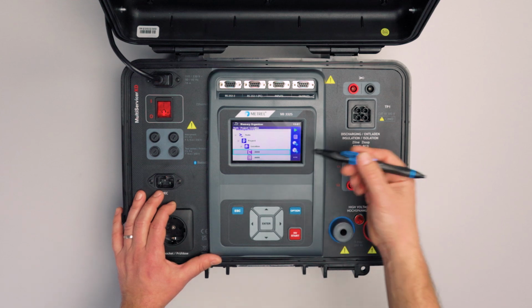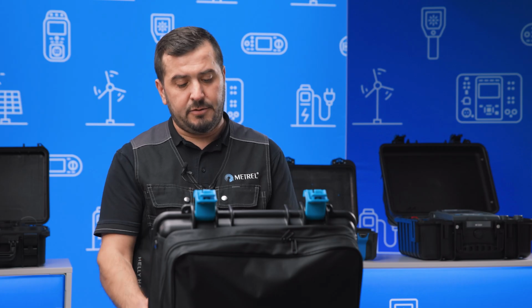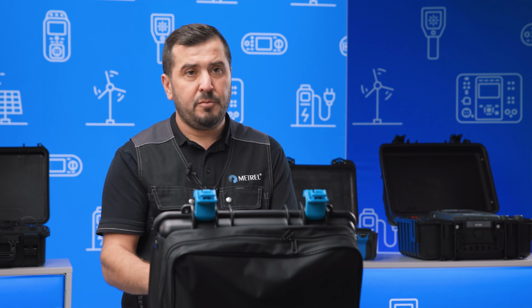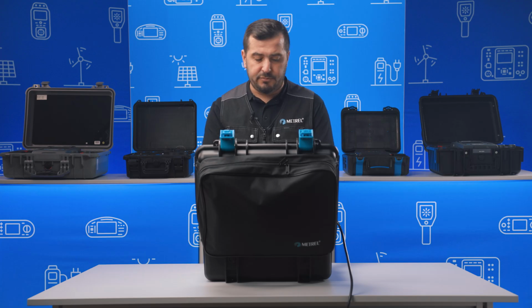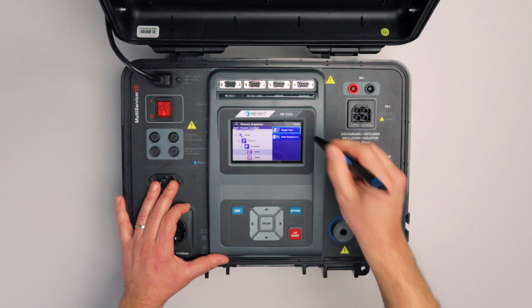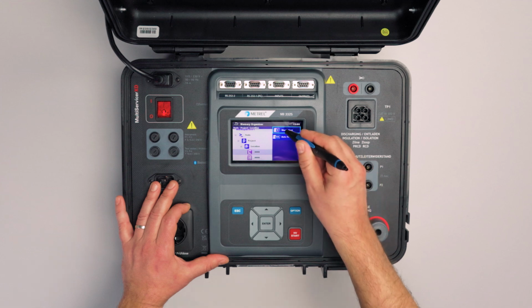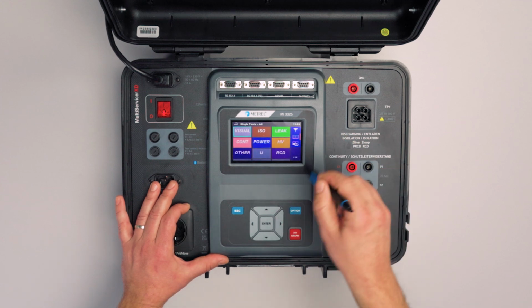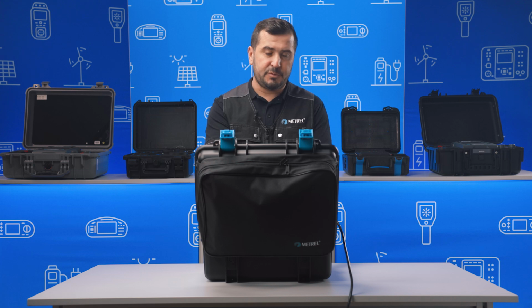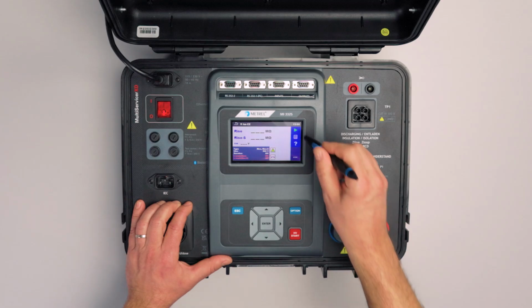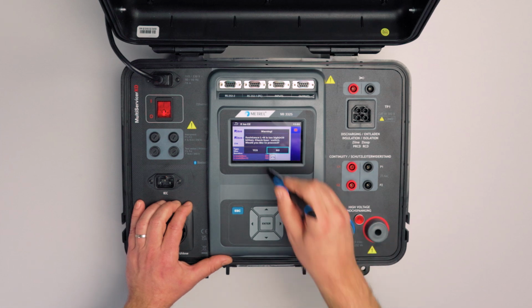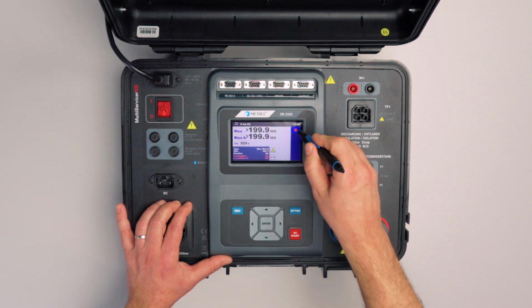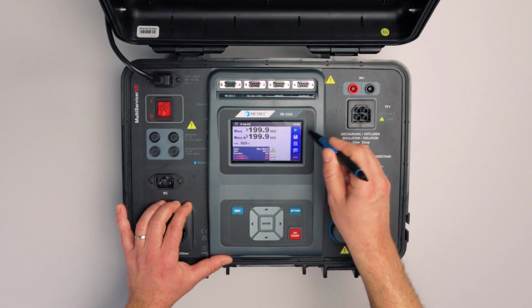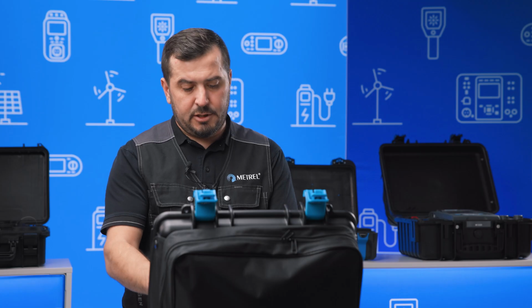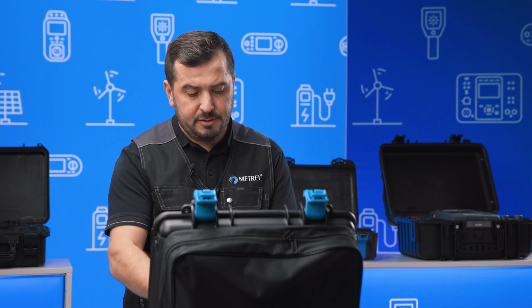So as I mentioned, we can simply create ourselves a structure by performing the measurement step by step on specific equipment. If we say we would like to test a switchboard, then we select the option single test, and the instrument will jump into the single test menu, where we select the specific or required measurement, execute it and save it under that location. Like this, stop and save. So now this is stored inside the memory organizer.